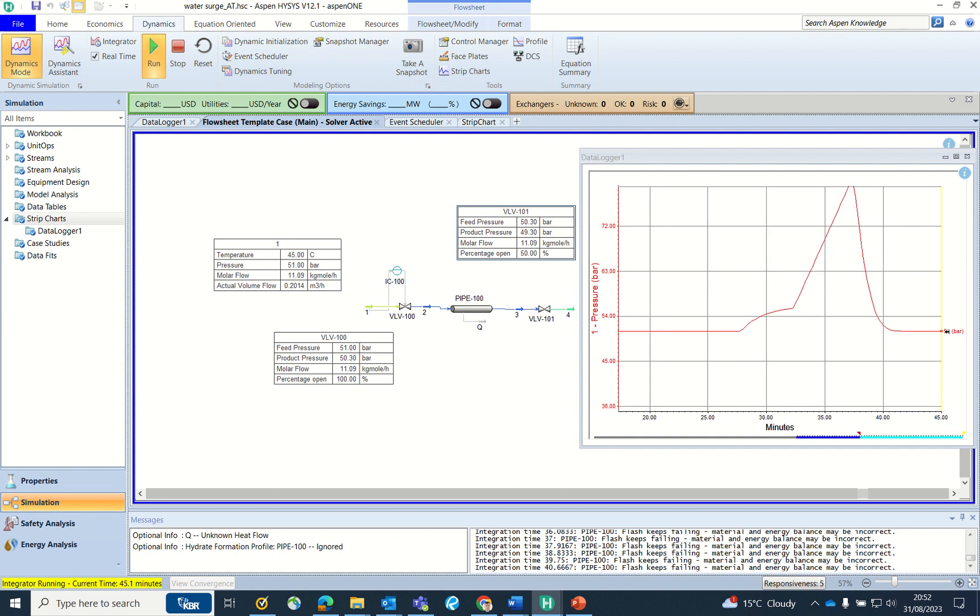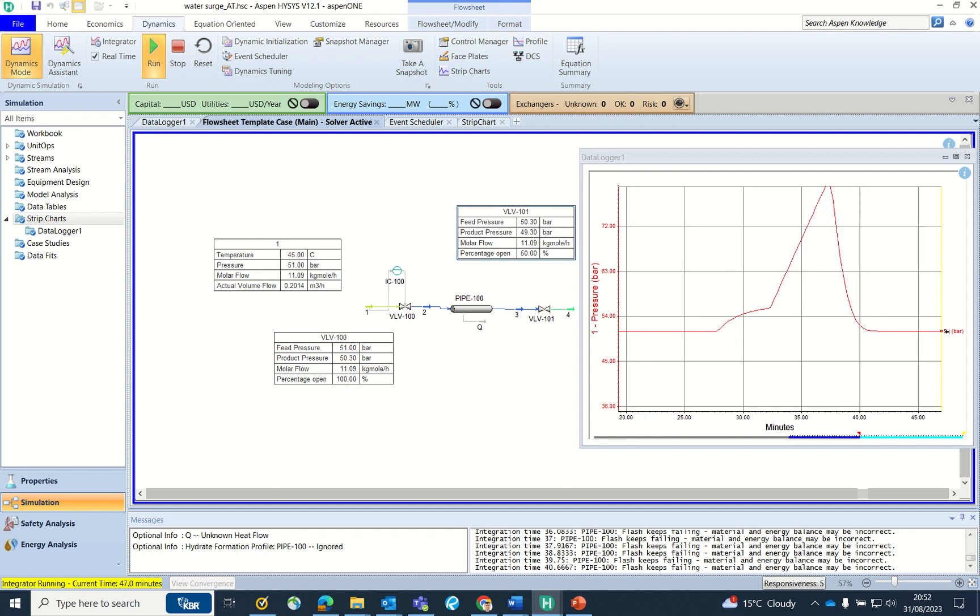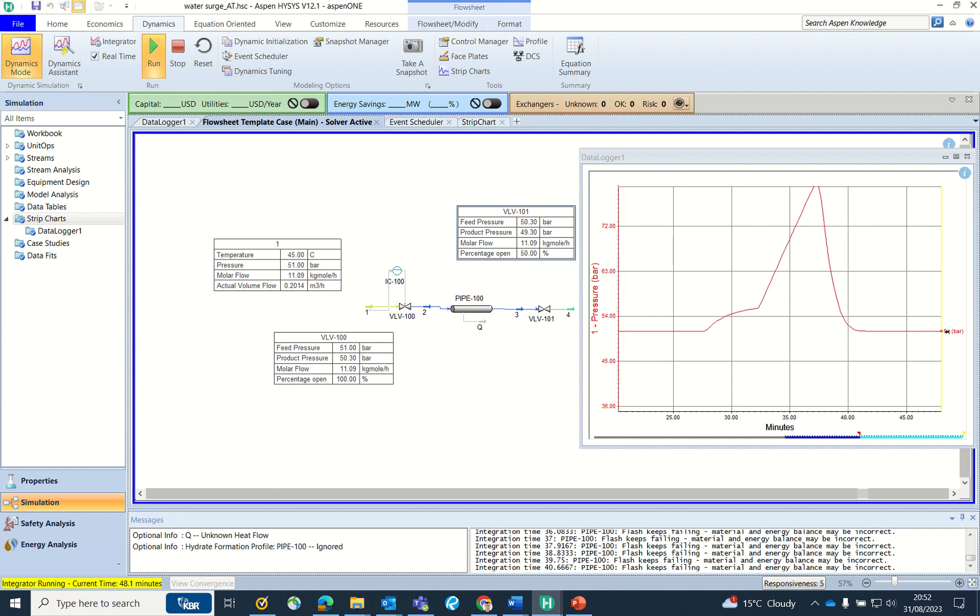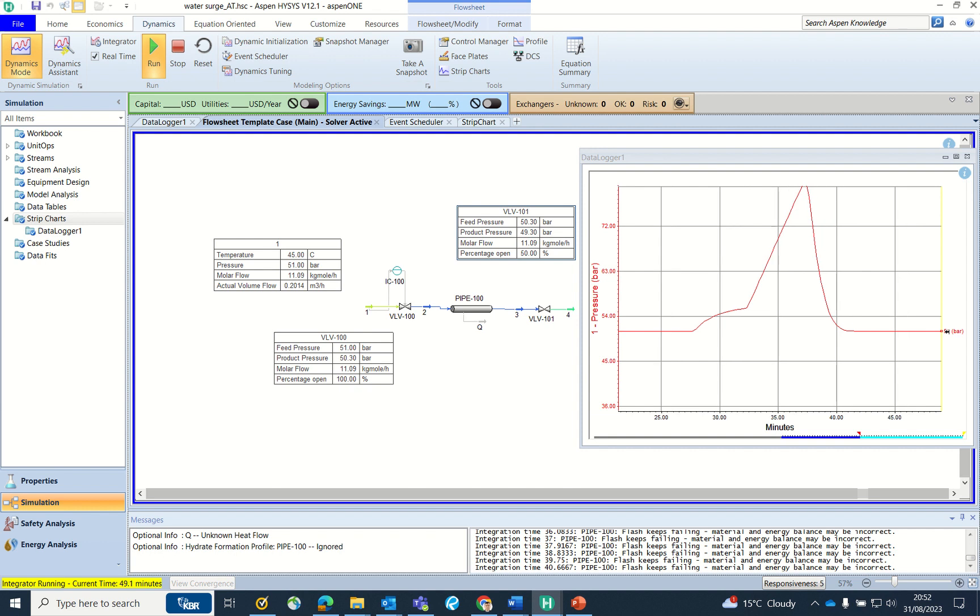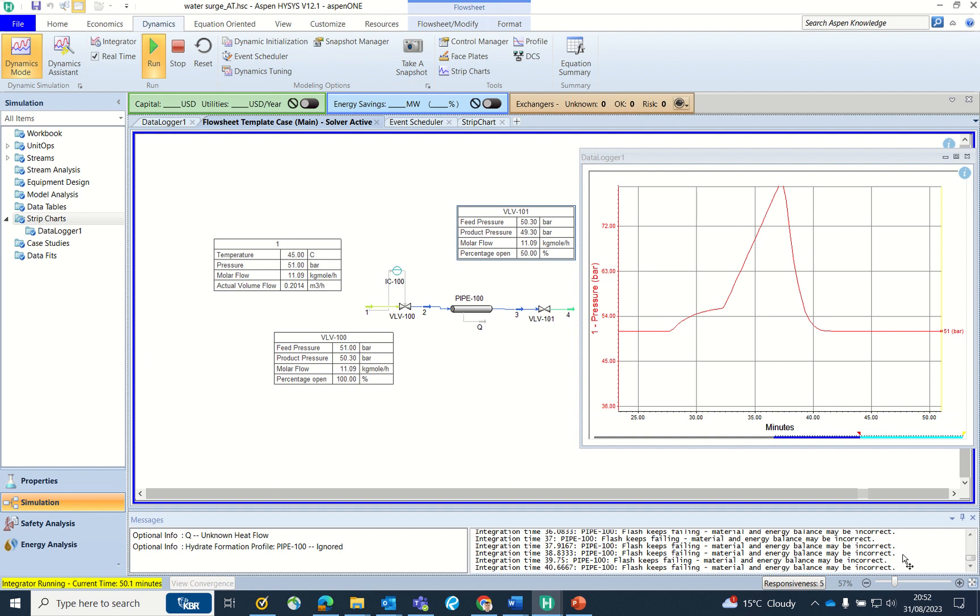In case the pressure goes above the pipe rating of say 150 pound rating, because it's schedule 40 it will be around 600 pounds, so if the pressure is above the 600 pounds by operating you have to provide the PSV to safeguard your pipelines. Otherwise, if the pressure rise is not much then you can say that okay, my PSV is not required on the line. This is a kind of experimental value or you can see how the HYSYS Dynamics predicts the rise in the pressure.